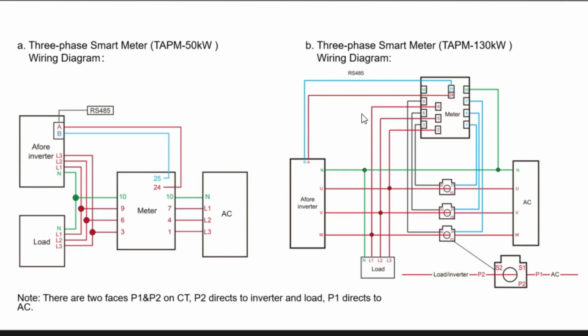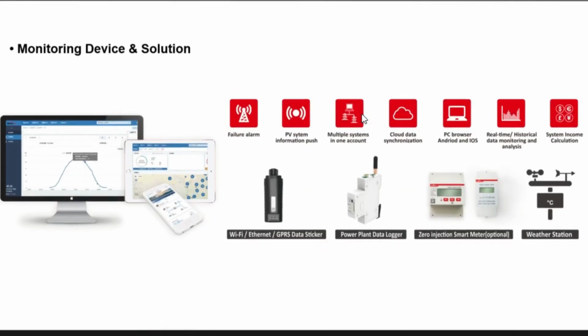So if the load is bigger than 500 kilowatts, up to megawatts, you only need to change to a different size ratio of CT, and that is enough. Every CT has a correct direction. On the CT there are numbers or arrows. When you connect the CT on the line, make sure this direction is the same as described. Otherwise, the inverter cannot detect the right direction of energy, and some of the operational modes cannot work smoothly because the detected energy direction is different.